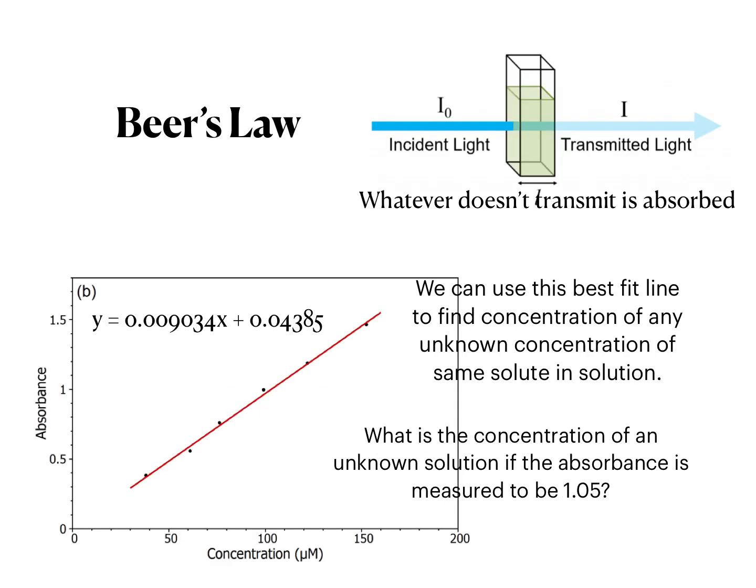Check it out. So inside the colorimeter, you have a sample of solution in what is known as a cuvette. It is this long rectangular looking thing, and it holds the liquid. What happens is that the light comes out from the light source, we call that the incident light, passes through the solution, and the transmitted light on the other side is going to be weaker or fainter than the incident light.